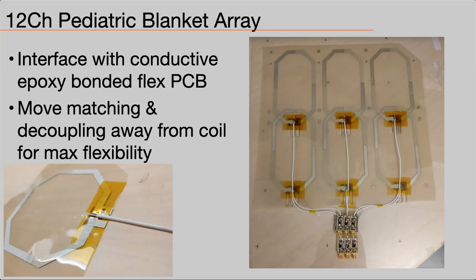Now, while the substrate and inks are flexible, we still need to connect the traces and add the matching, tuning, and detuning circuitry that we showed before. In this example of the posterior portion of a 12-channel pediatric blanket array, we interface to the printed coil via a flex PCB bonded using conductive epoxy. To avoid any bulky components within the antenna portion, we move the matching and detuning circuit away from the coil, so you have pretty much a transmission line that takes you over there. But that also makes the transmission line part of the entire coil, which is usually not the case in traditional coils. This is a compromise that is done in order to maintain flexibility. So now you have a flexible device here, and this is not necessarily so flexible anymore.